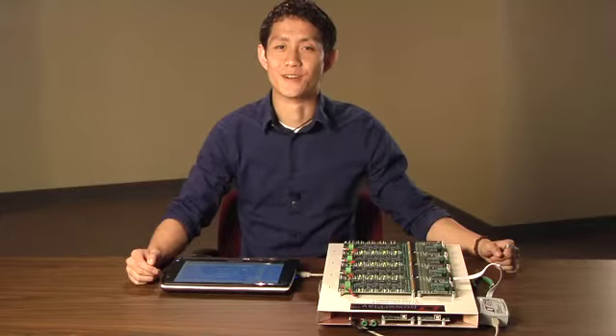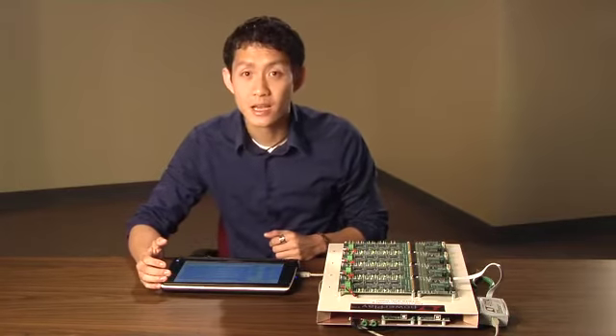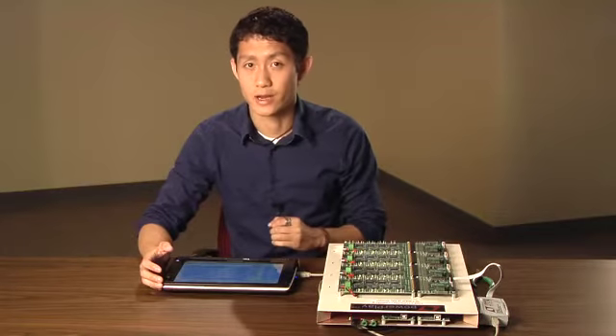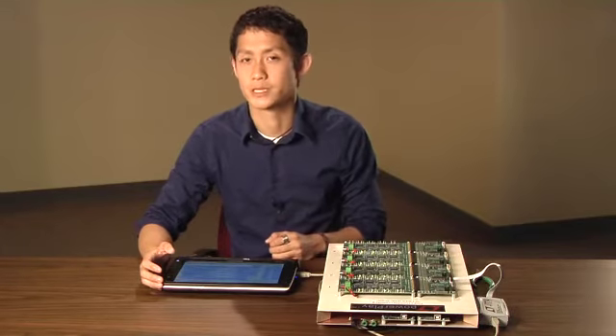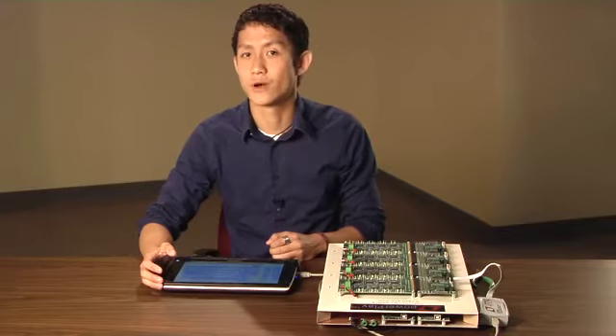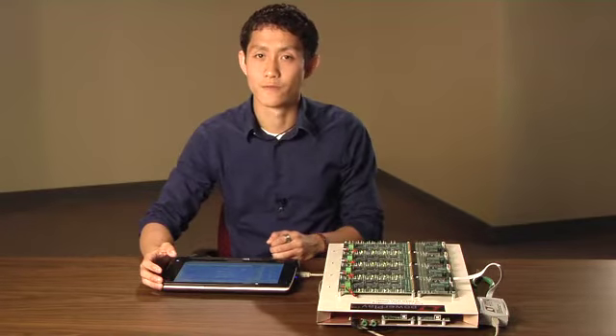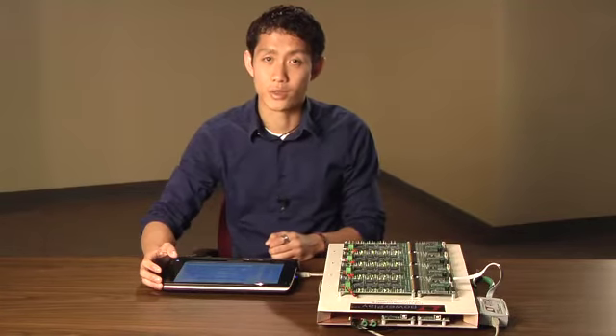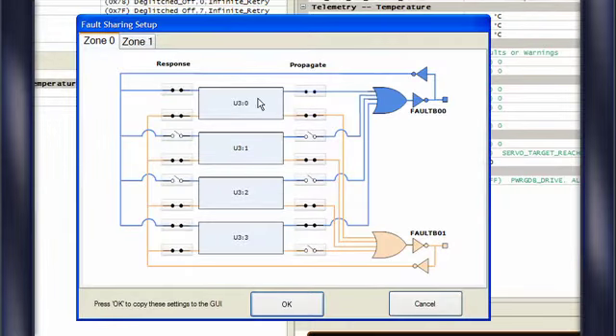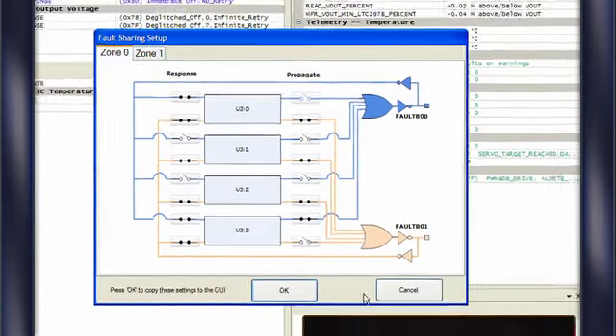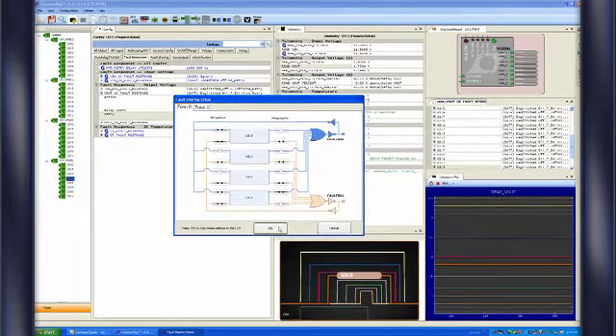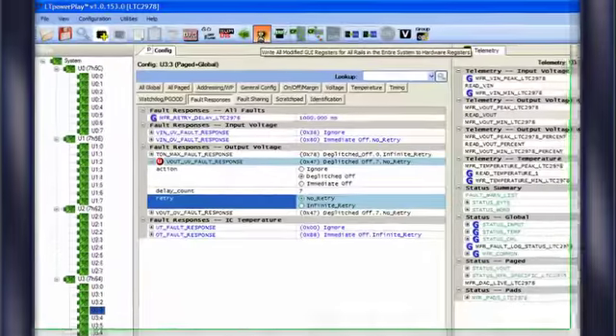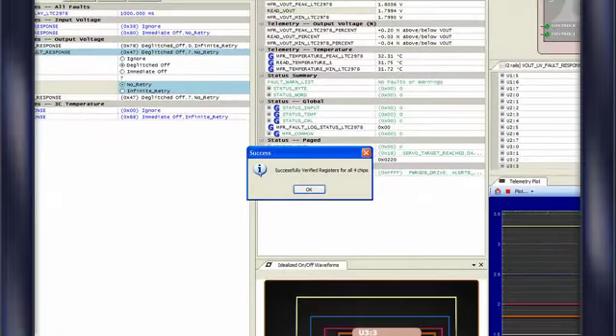But let's have a little more fun. We can easily reprogram the LTC2978 to have a different fault response on each channel. Here, I've changed the configuration so that a fault on channel 3 only propagates to channel 0. I've also modified channel 3's fault response to not retry a power-on sequence when an under voltage fault is detected. Channel 3 will fault off and stay off and it will bring channel 0 along with it. I've not modified the fault propagation or response of the other channels. I can close this window and write the new configuration to hardware. I can also click this button to store the configuration into non-volatile memory so that this configuration is recalled during subsequent power-ons.